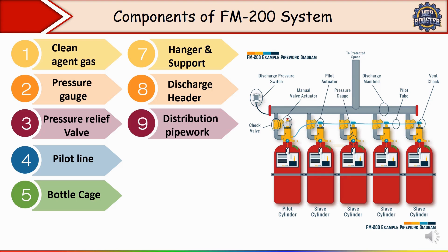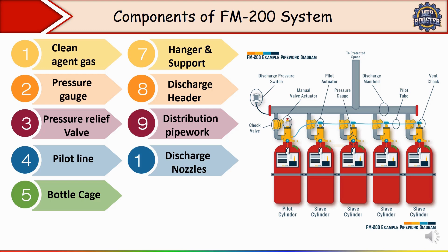Distribution pipework consists of pipes used to transport the FM-200 gas from the cylinder to the discharge nozzle. It is designed to deliver the gas evenly across the entire protected area, and must be sized and installed correctly to ensure proper flow rate and pressure distribution. The next component is the discharge nozzles — specially designed nozzles placed throughout the protected area that discharge the FM-200 gas into the room or enclosure. Finally, the control panel receives signals from smoke or heat detectors, activates alarms, and initiates the discharge of FM-200 gas. It also provides feedback on system status and can manually trigger or stop the discharge.